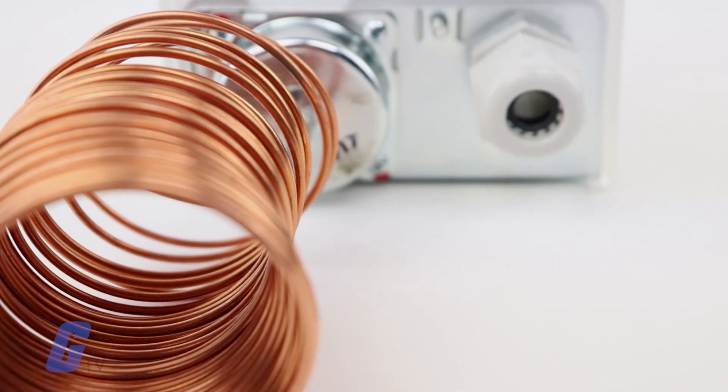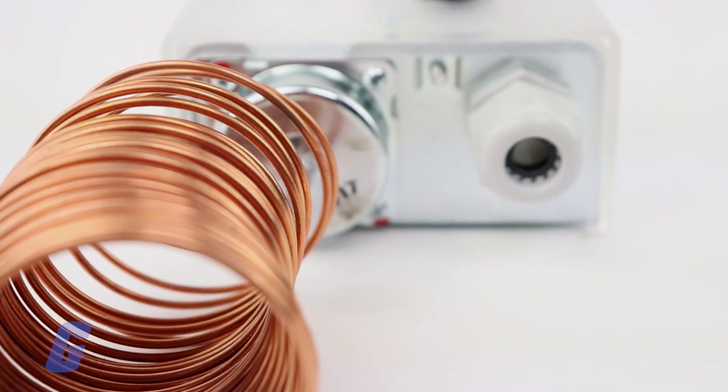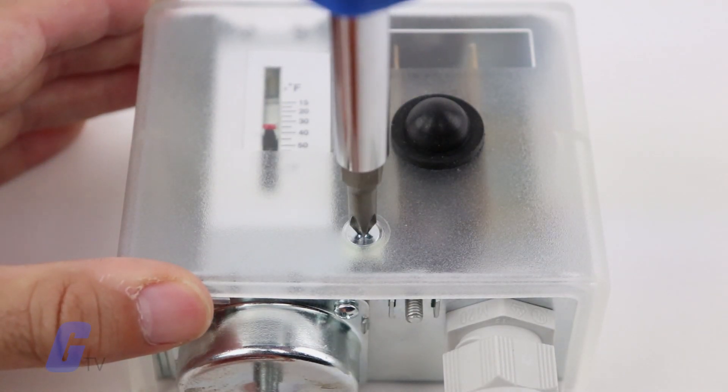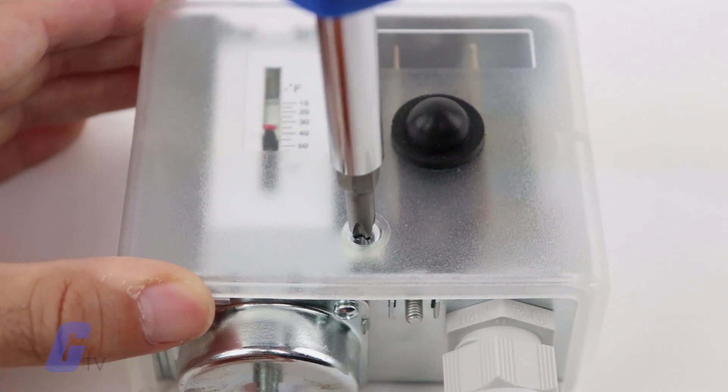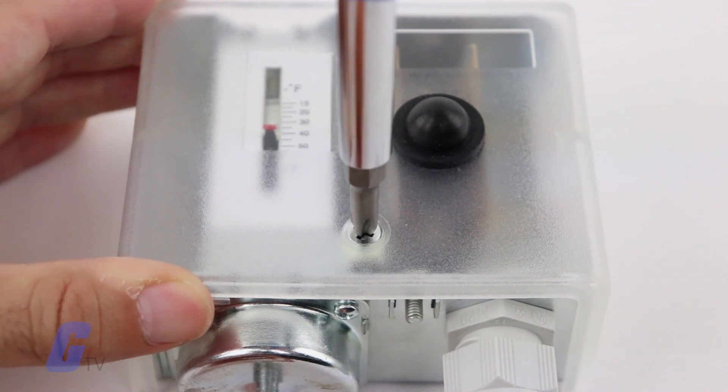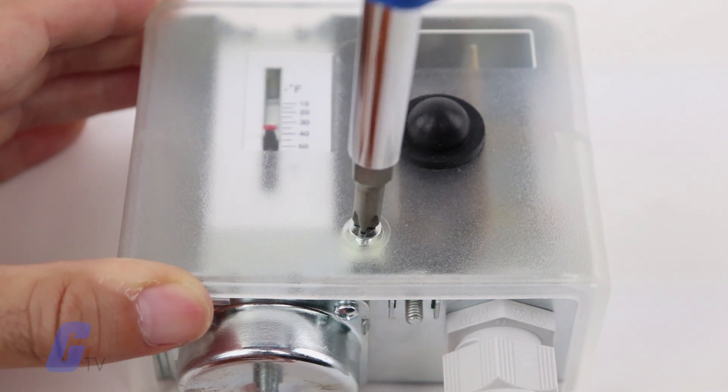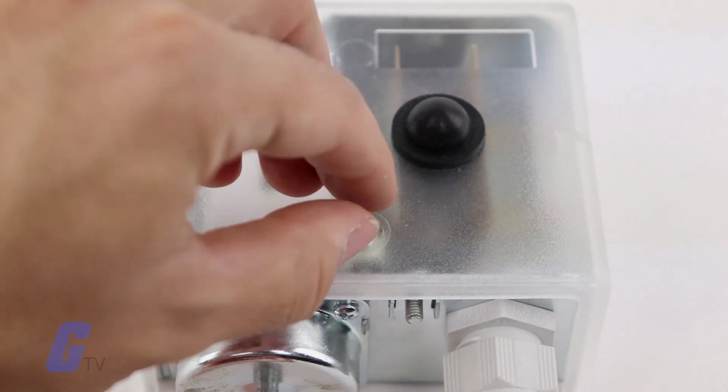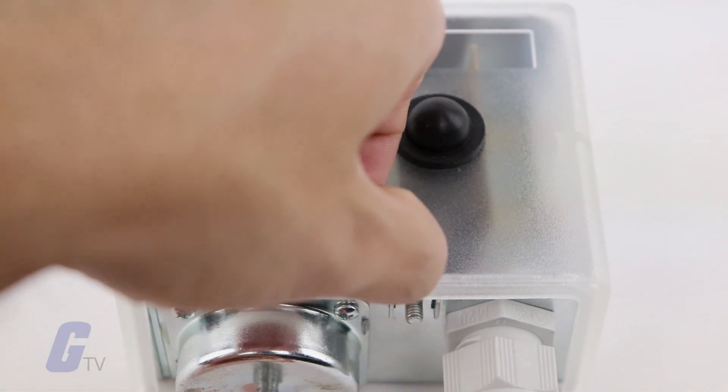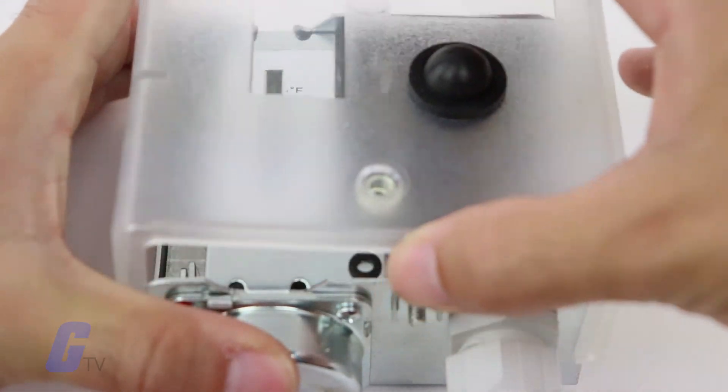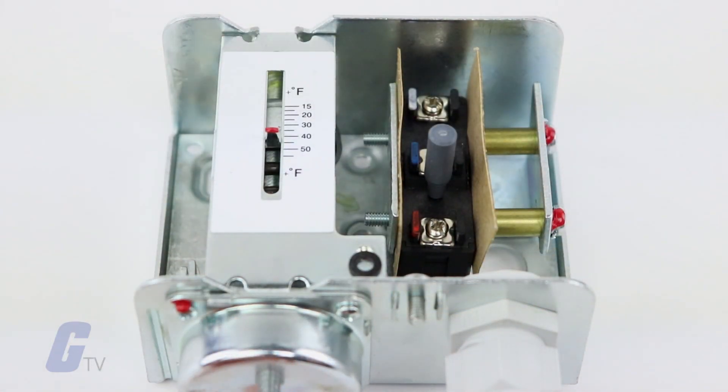Any one-foot length of the sensing element subjected to temperatures below the cutout setpoint setting of the thermostat will actuate the thermostat switch mechanism regardless of the temperature being sensed by the remainder of the element.